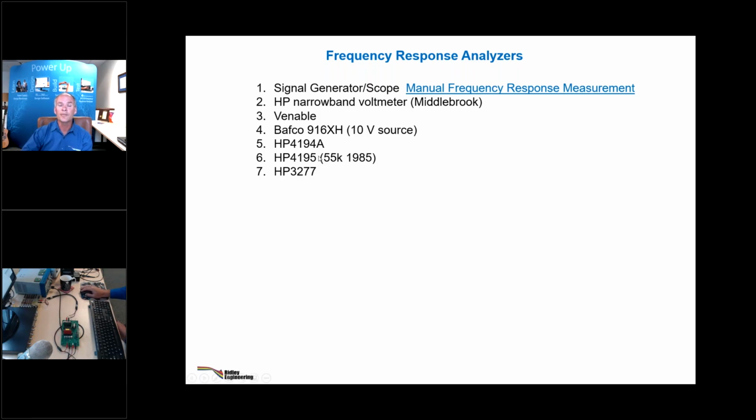So you can still find them. If they work, great. If they don't work, it can be hard to repair. HP stopped servicing them for a while. I think they've started that again. But these can cost up to 7K just to repair the input channels, because nobody has the parts anymore for those.